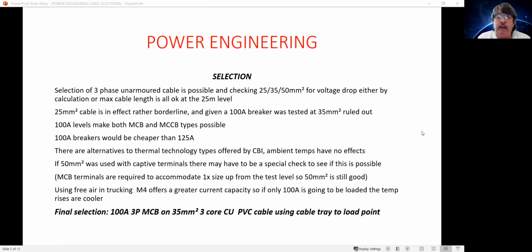The molded case we need to have a look at, because if we were to, let's say, go with the 50 mil cable, because we had that in our toolbox and we've got 25 meters of it, why not? Well, why not indeed? It's paid for, it's done, it could go in there. The only requirement is you'd have to look at the captive terminals, because miniature circuit breakers generally are not lug type connections. And you'd have to look at whether the 50 mil would in fact fit inside the captive type terminal.